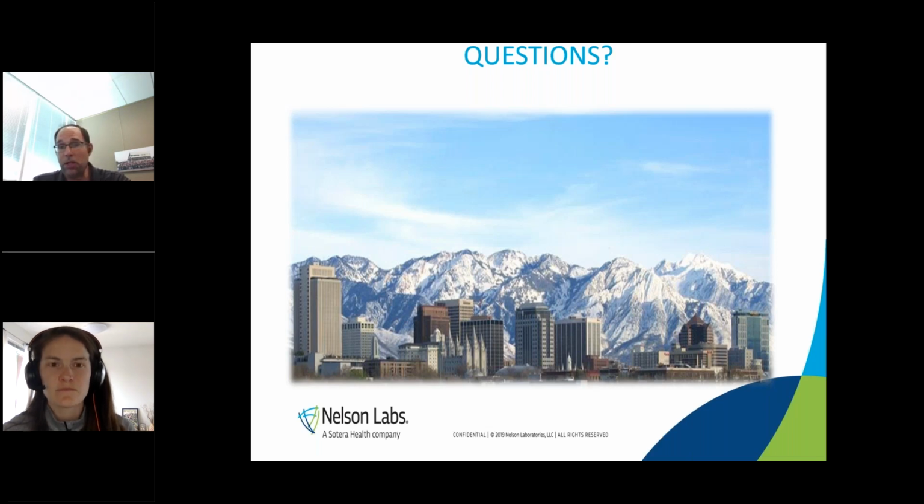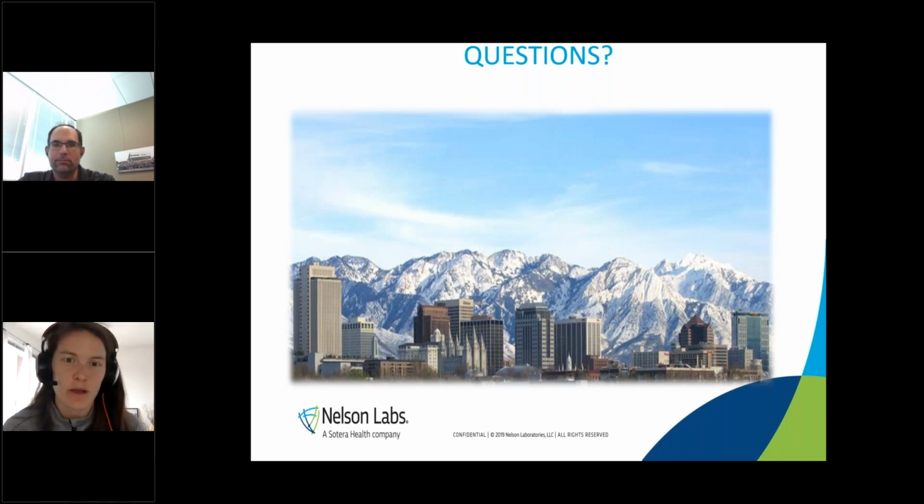So Taylor, what are your thoughts? Over documentation is always a passion of mine. Again, being a quality person, I am obviously keen on Greenlight Guru's way we have our risk management set up, and so including both 10993 and of course 14971 and marrying the two. Maybe there's something you do with additional labels or tagging on risk items to say this specific mitigation or this specific hazardous situation is somehow related to biocompatibility, just so you can search through your big long matrix and see if asked how you're meeting the requirements of 10993. Yeah, that's a shortcut. Good suggestion.